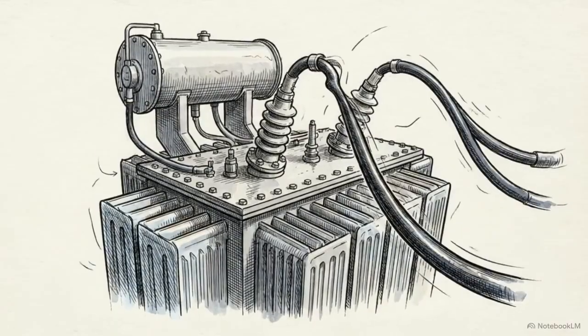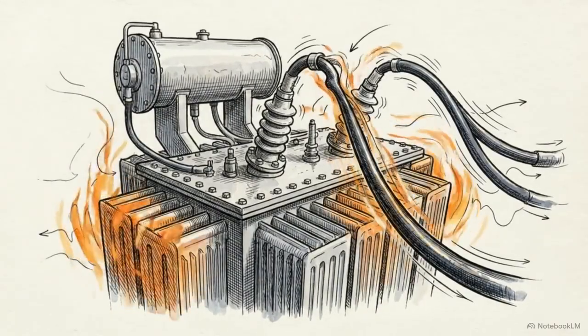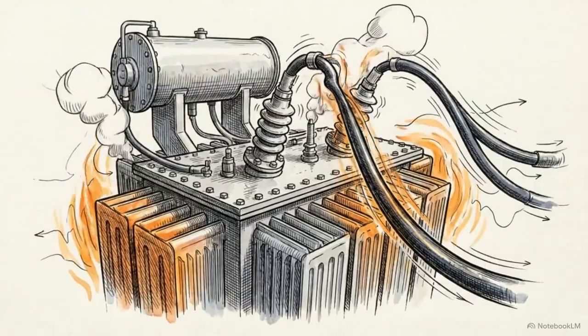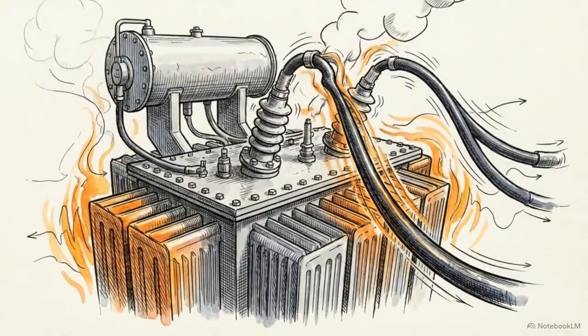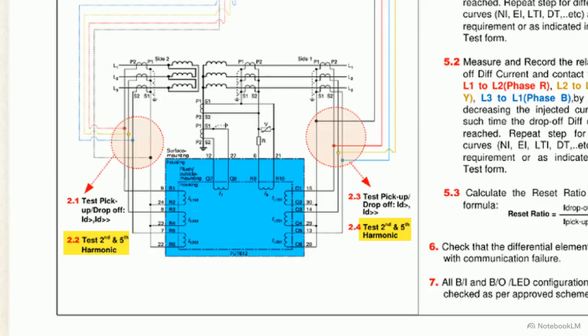Transformer differential testing adds a layer of complexity. Because powering up a transformer draws a massive, unbalanced inrush current, technicians must inject second and fifth harmonics during testing. This proves the relay's logic will recognize the harmonic signature of an inrush and successfully block a false trip.